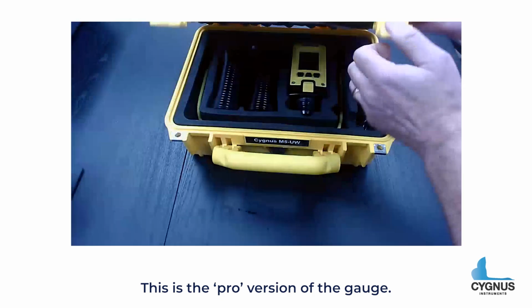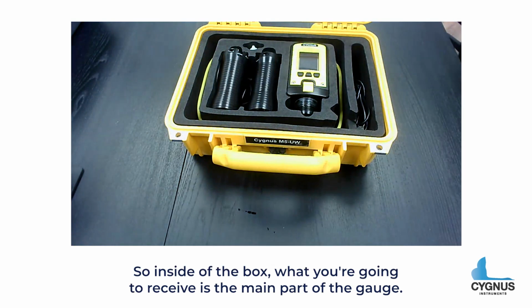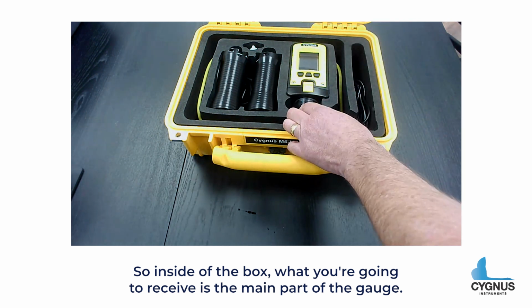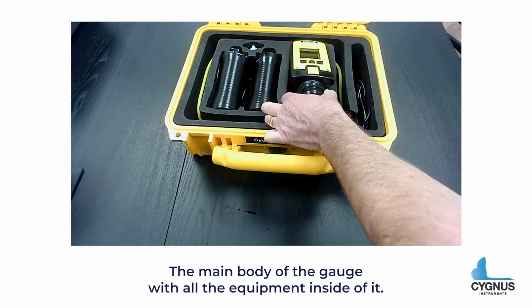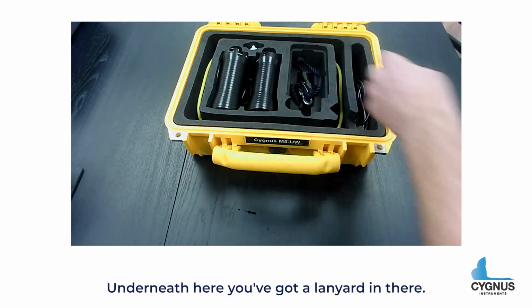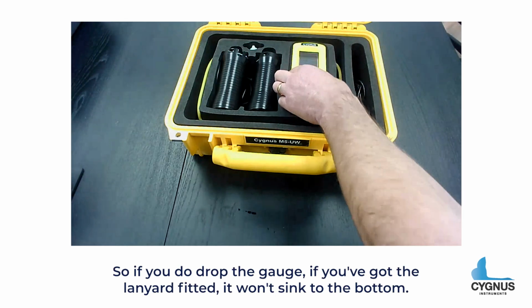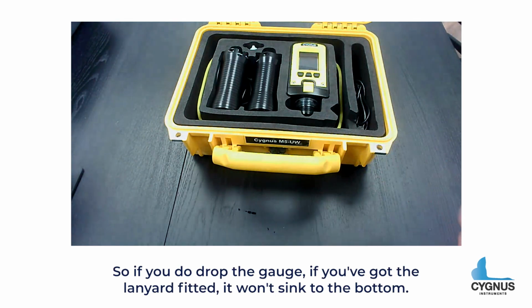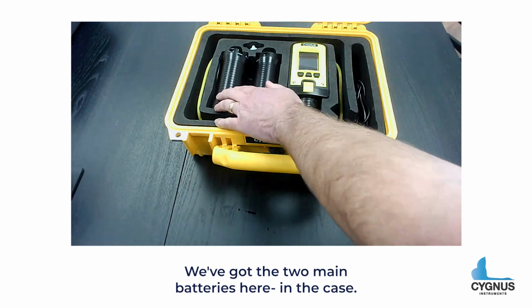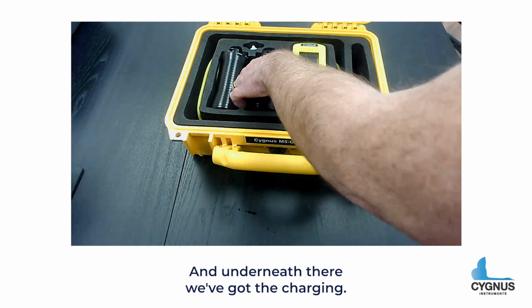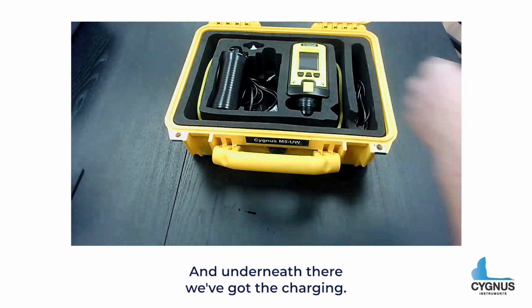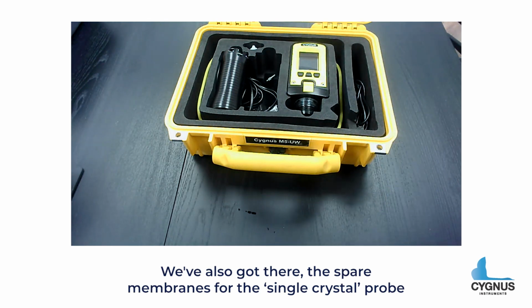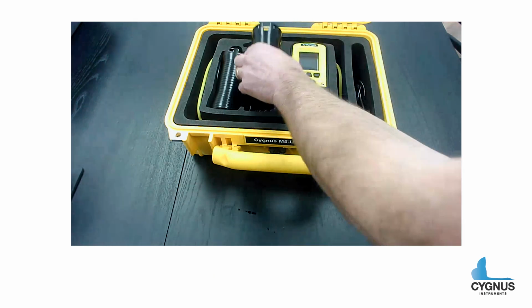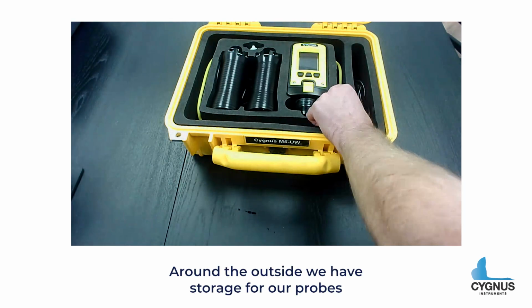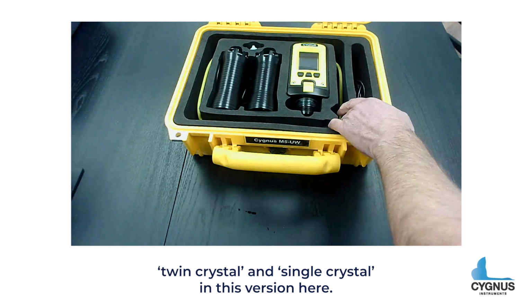This is the 'pro' version of the gauge. So inside of the box, what you're going to receive is the main part of the gauge, the main body of the gauge with all the equipment inside of it. Underneath here, you've got a lanyard in there. So if you do drop the gauge, if you've got the lanyard fitted, it won't sink to the bottom. We've got the 2 main batteries here in the case, and underneath there we've got the charging. We've also got there the spare membranes for the single crystal probe. Around the outside, we have our storage for our probes, twin crystal and single crystal in this version here.